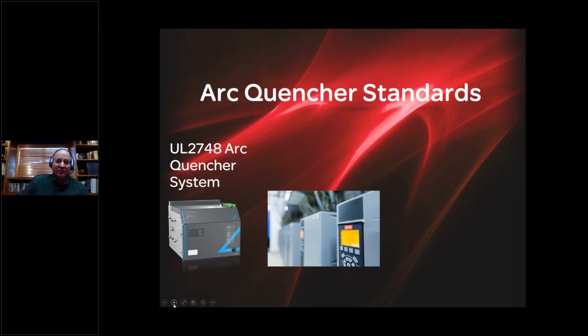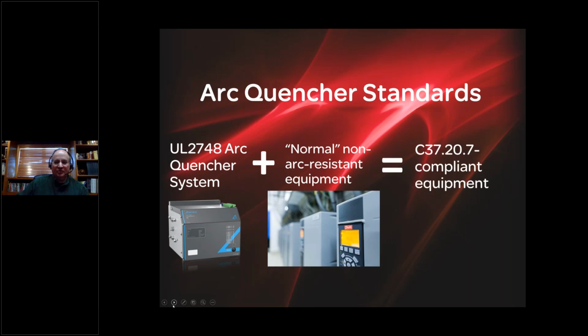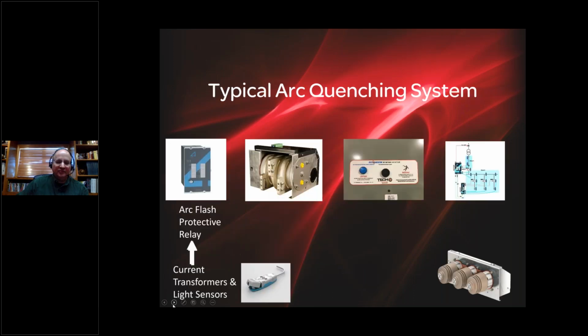We take an arc quencher system, and we add that arc quencher system to the standard normal non-arc resistant equipment, and we achieve C37.20.7 compliance. But again, there's a caveat here. Those drives must be type tested in order for us to achieve that.